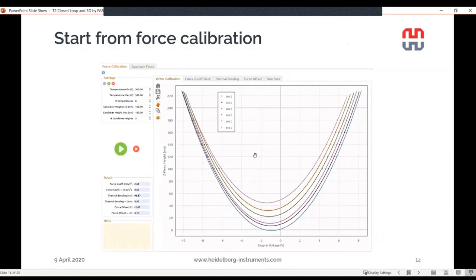And I want to mention one thing. You can do this if you are working with a cantilever that you don't know yet from a certain batch, and then you will get a set of parameters. But if you use a cantilever from the same batch that has very similar parameters, you essentially don't have to do this again, because the result will be quite similar. And also, the control loop will anyways optimize the parameters for you much better than this calibration can do.